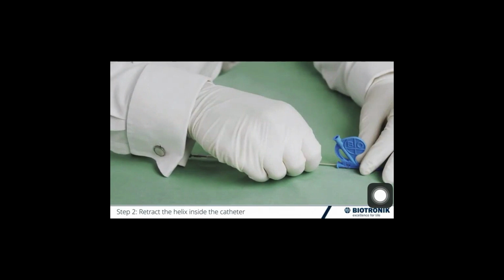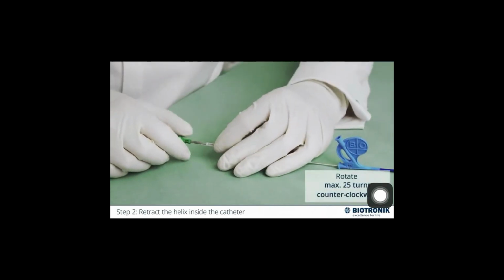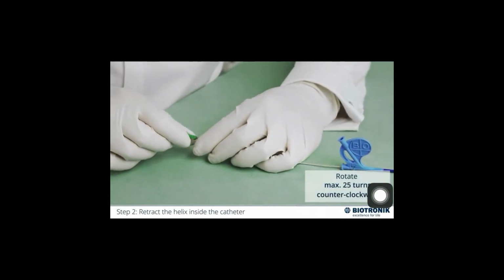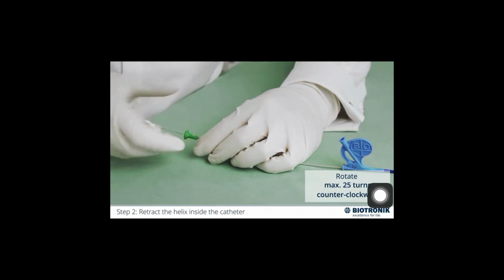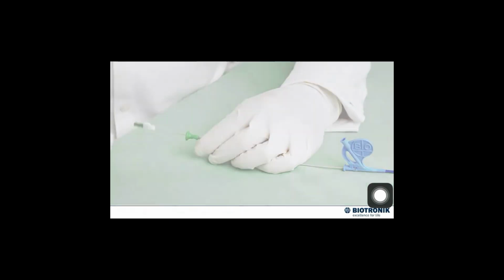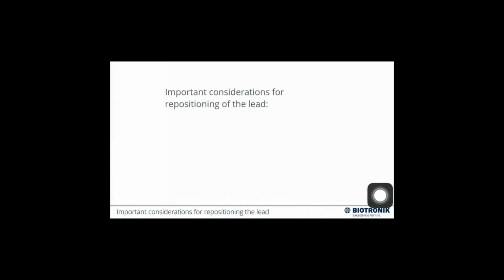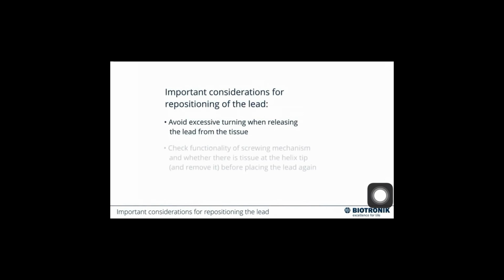After removal of the lead from the tissue, the screw can be retracted by turning the pin counterclockwise using either the fixation tool or the green stylet guide. Avoid excessive counter-turning of the lead body during repositioning. Too many turns can damage the lead. Before repositioning the lead, remove the lead from the catheter, check the functionality of the screwing mechanism again and whether there is tissue at the helix tip.